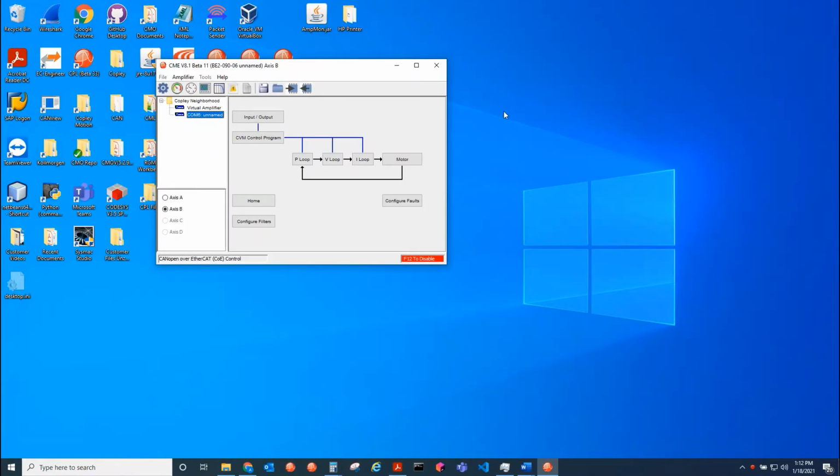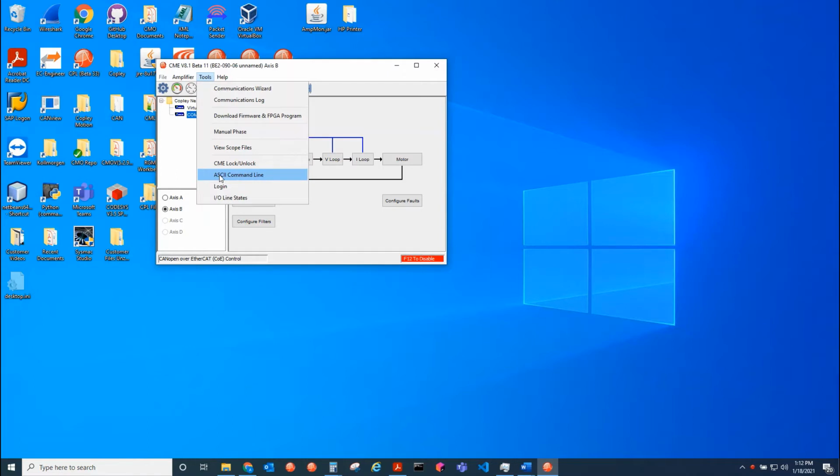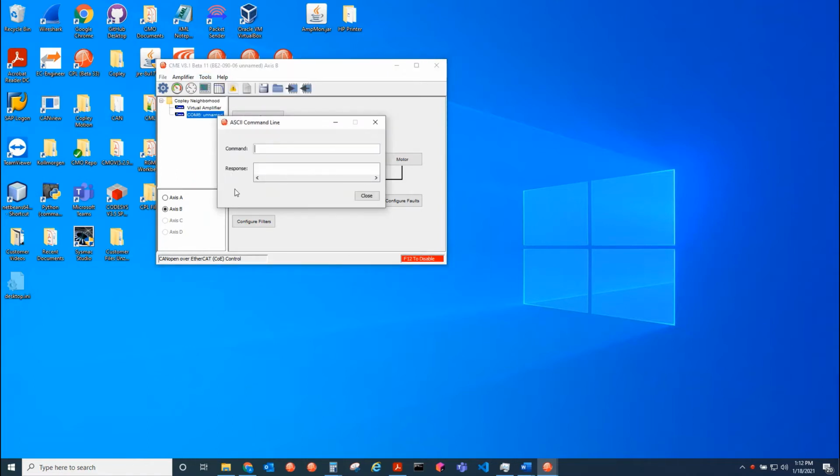So what does that do when you load the Ethernet firmware? Well, it gets rid of all the EtherCAT firmware and it puts in special Ethernet capabilities. So with Ethernet you can talk TCP/IP, Modbus TCP, and a bunch of other Ethernet protocols. If we get the network options parameter, we see that bit 9 is set, and that's how you can tell that it's Ethernet firmware.